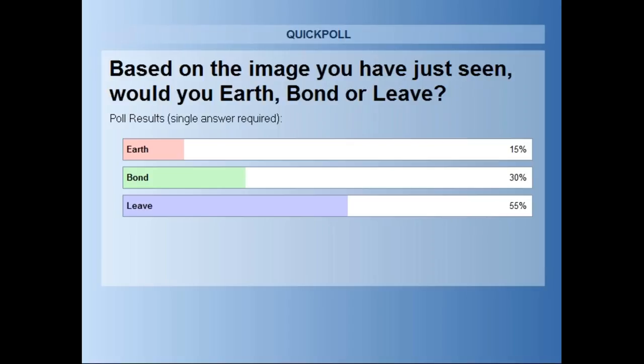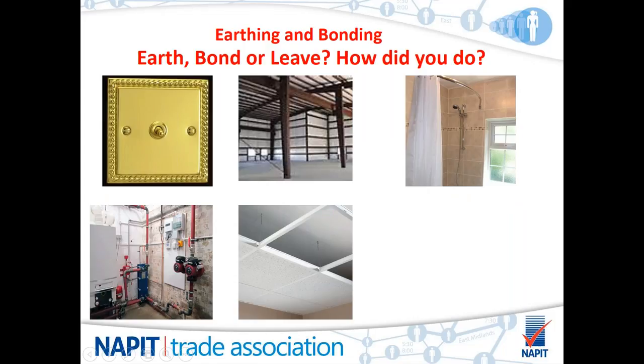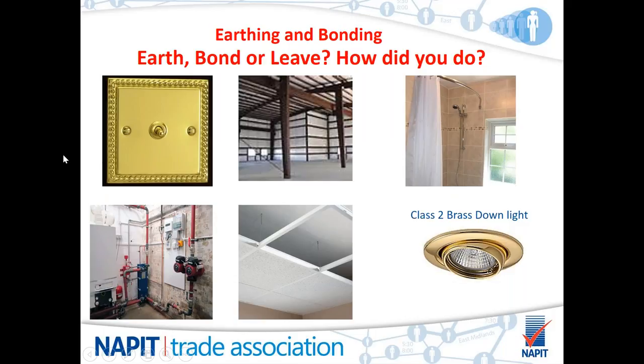And the answer is actually to leave it, yeah. It doesn't need earthing. It doesn't need bonding. It is not a support system. It's not there to take the weight of cables. Cables should not touch this. It would actually be indirectly earthed from the metal modular light fittings that you place in the grid. But it doesn't need earthing itself. The light fittings themselves need earthing because they're exposed conductive parts. But the grid, no, it's not a part of the electrical system, and therefore it does not need earthing or bonding. It should be left alone. And the last one is a class 2 brass downlight. We asked you the same questions, and so we'll open up the poll one more time, see what you come up with.